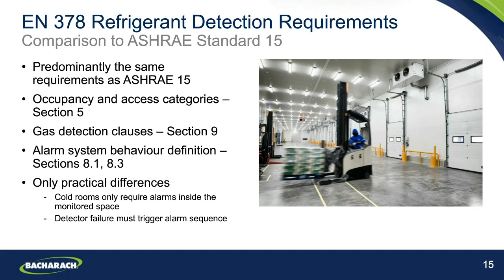But to cut to the chase, the only practical differences between these two regulations are that within the European standard, cold rooms only require alarms inside the monitored space. There is no specific mandate within there to alarm audibly and visually outside of the entrance. And in the event of a detector failure, the alarm sequence must also be triggered.